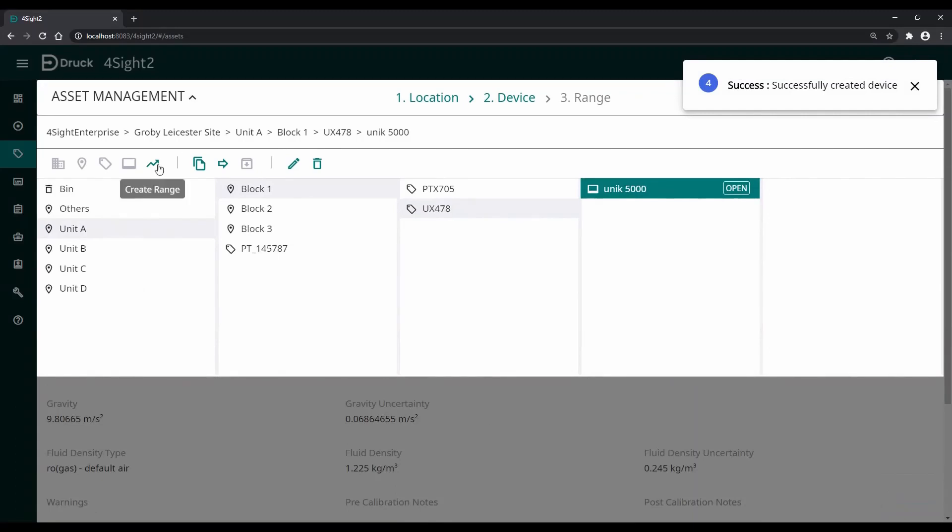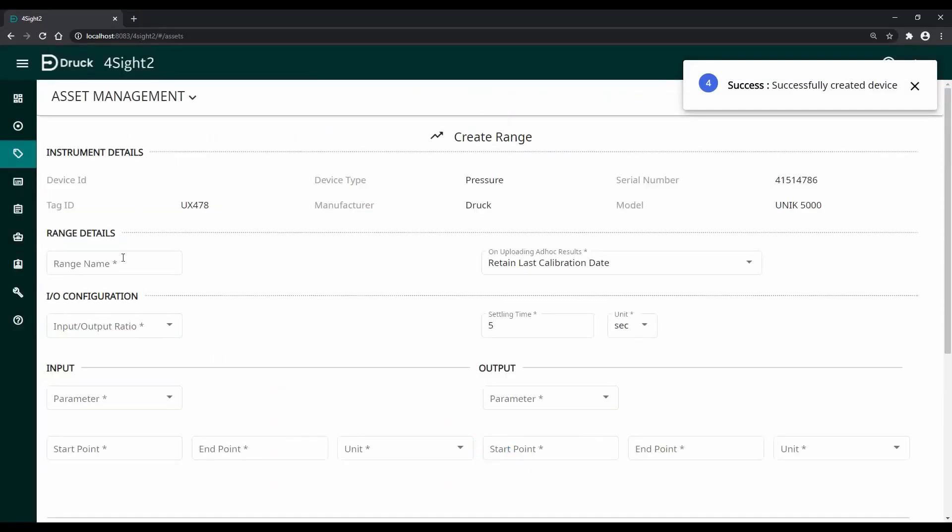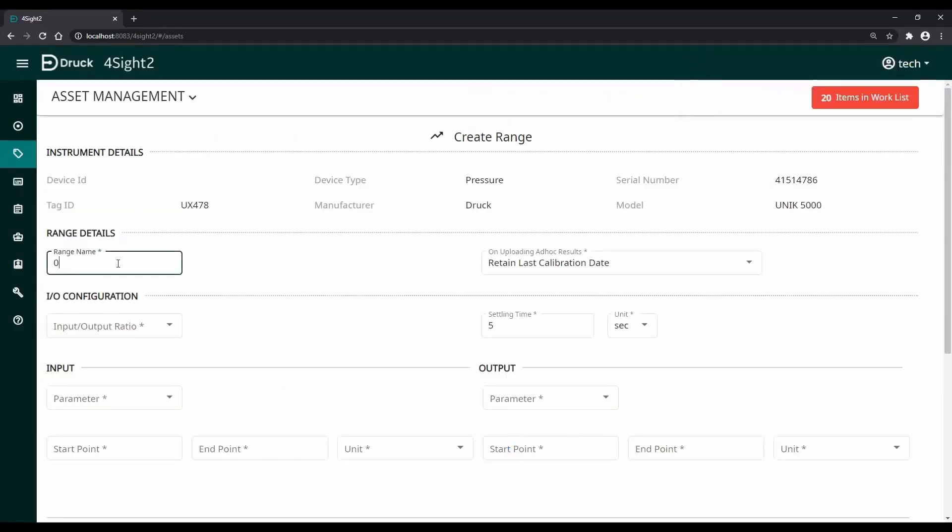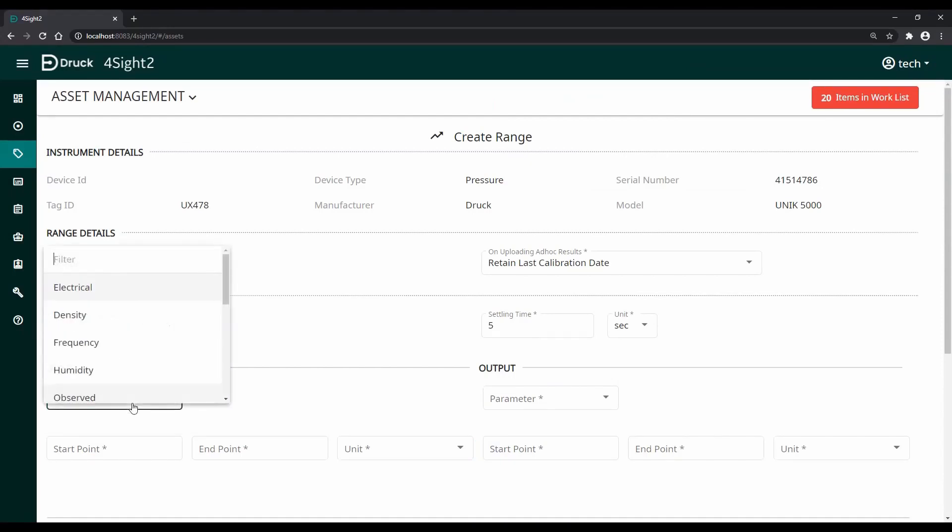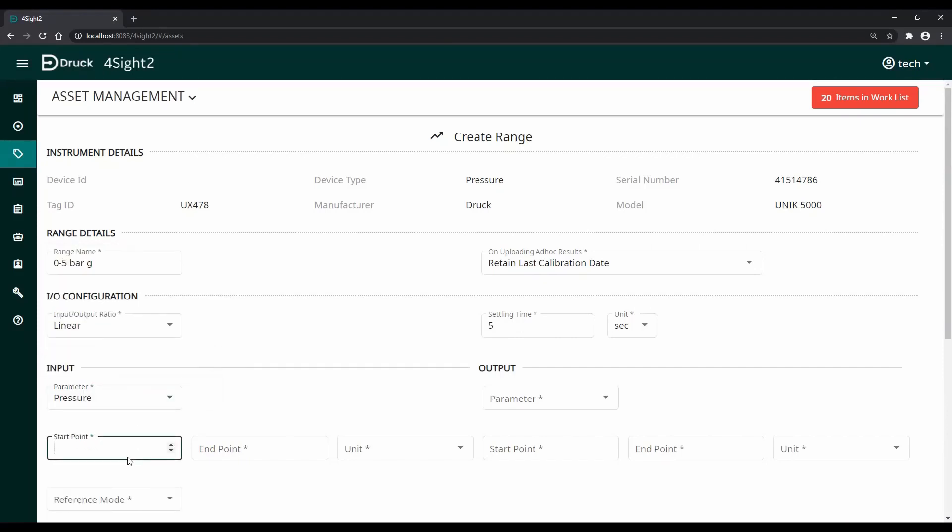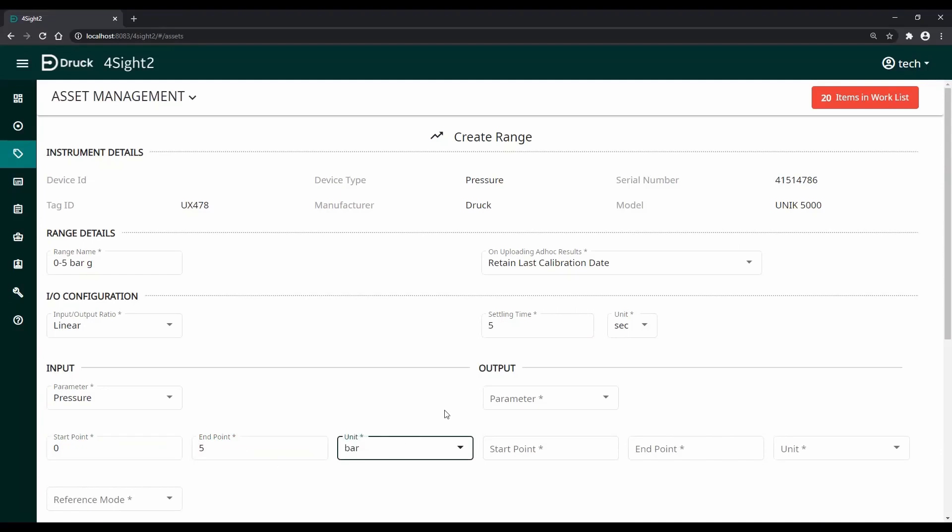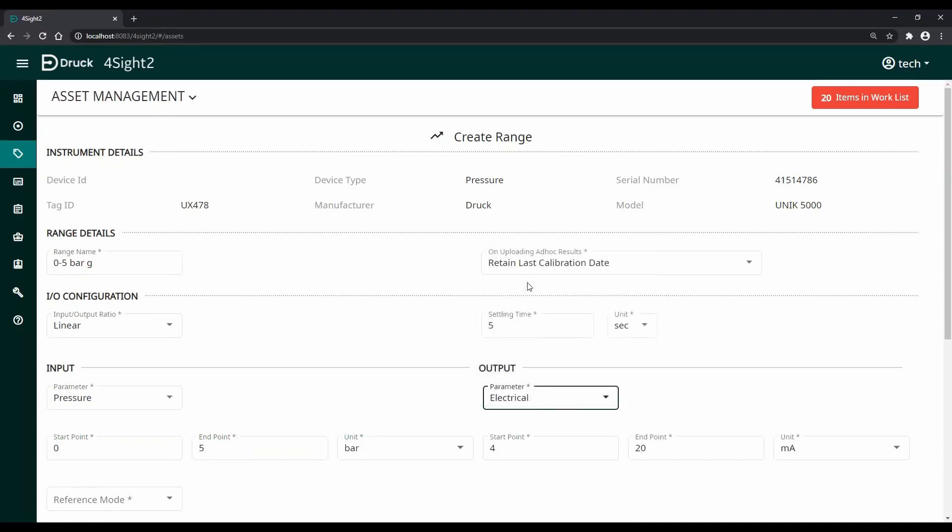The third and final step is to add one or more range. This is where we will add our input and output for the sensor. This is a pressure sensor which is 0 to 5 bar input and the output is 4 to 20 milliamps.